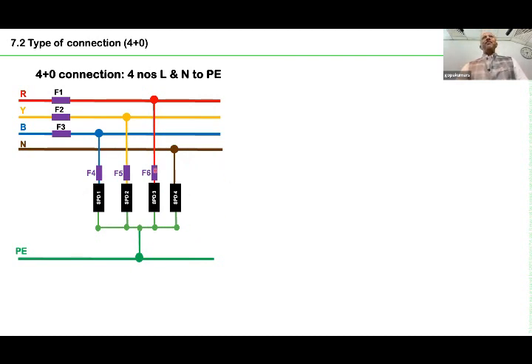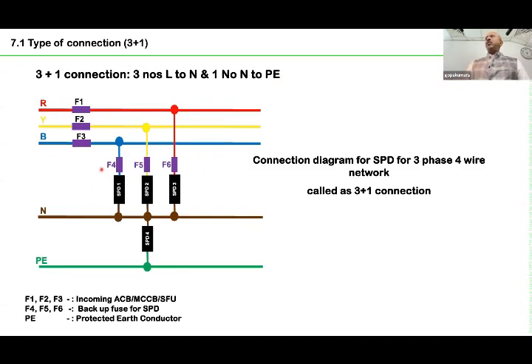But the problem is, if you have a TT system, you cannot trust these fuses, because in a TT system, fuses will not blow because the fault current is quite low. The fault loop impedance and those things come into the picture, which is not even addressed in the standards so far. So the best recommended way is, if you go for a TT system, don't go for a 4+0 connection, go for a 3+1 connection, the previous connection. So this is good for a TT network. But ensure that the line to neutral SPDs are always 440 volt TOV withstand. Otherwise, that SPD fails.